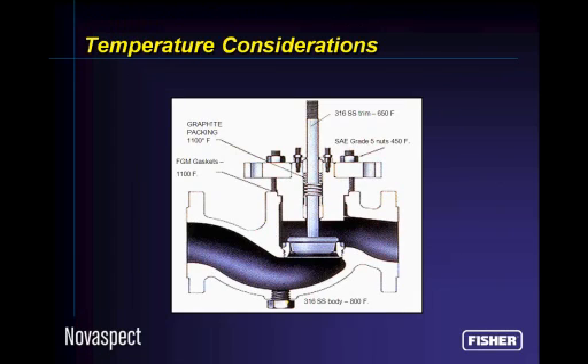We need to know the process fluid temperature. In addition to the wall thickness issue, we've got a bunch of parts inside that are not even actually pressure boundary parts, and therefore they're not part of the ANSI pressure class consideration, but nevertheless different metallurgies of parts in the valve have different temperature characteristics as far as how much temperature they can stand without degradation.